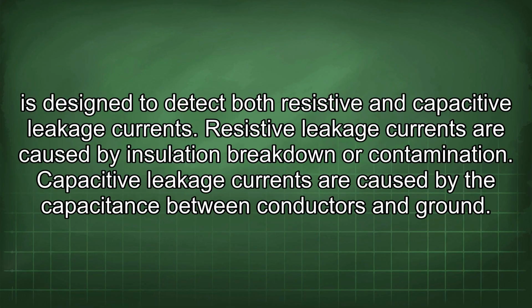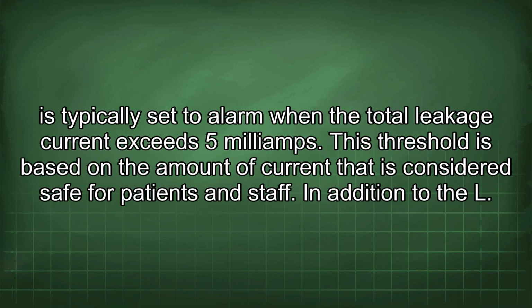The LIM is designed to detect both resistive and capacitive leakage currents. Resistive leakage currents are caused by insulation breakdown or contamination. Capacitive leakage currents are caused by the capacitance between conductors and ground. The LIM is typically set to alarm when the total leakage current exceeds 5 mA. This threshold is based on the amount of current that is considered safe for patients and staff.